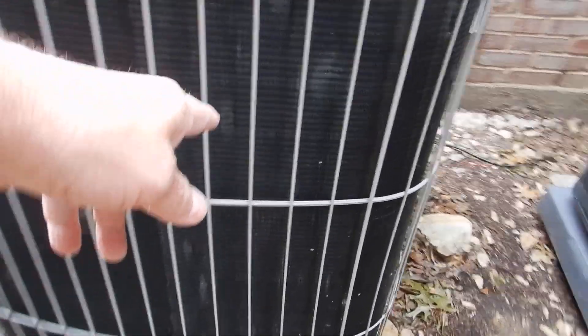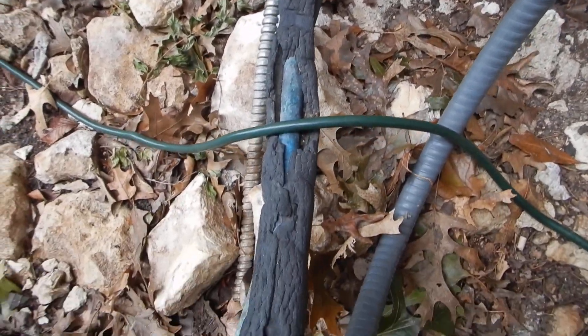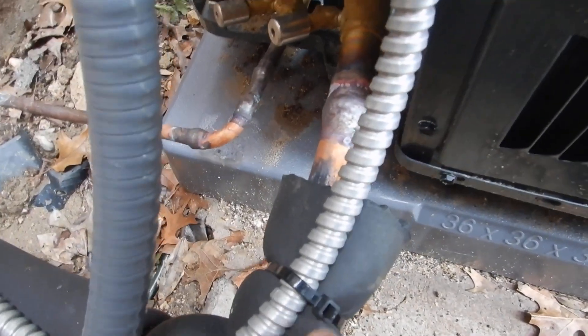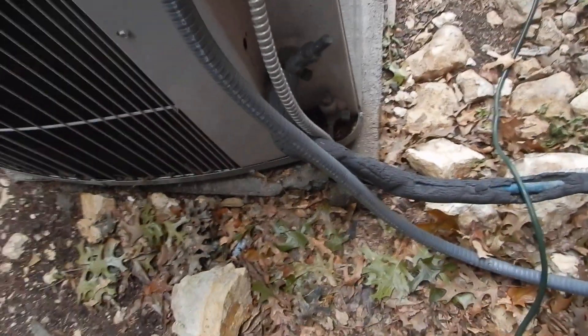Coming along here, it looks like there's a little bit of hail damage on these fins. Our refrigerant piping is supposed to be a nice solid robust piping, and we're supposed to have anti-theft Schrader valve caps on this newer unit. We do have anti-theft Schrader valve caps, but we do not have the robust piping. We have the old-school pipe insulation — we should not have that; that's what we should have had here.